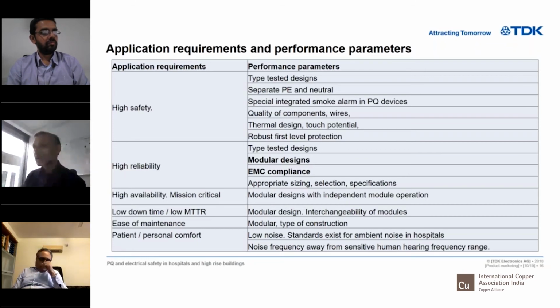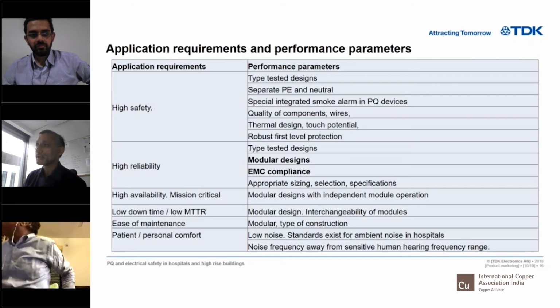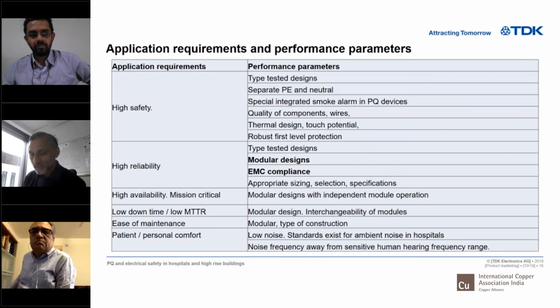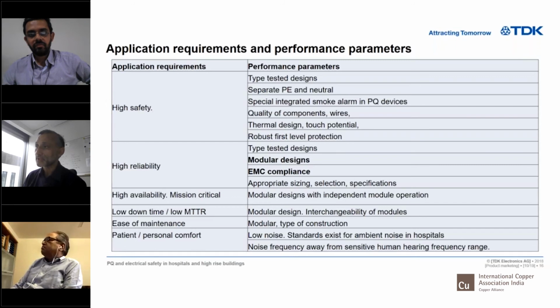when there's a fire. So when you're talking about high safety, everything right from cables to switchgear to power conditioning equipment especially should be a type tested design. And there must be a separate neutral and protective earth. Especially in India, even a good electrician would not know the difference between a neutral and an earth. We think the protective earth is the fourth wire, which is also the neutral, which is the cause of half the problems. Then in most cases, if you read the Abu Dhabi ADDC standards, even for a simple APFC panel, they started specifying five years back that the equipment should have an integrated smoke and fire alarm, so that the PQ device, when it catches fire, doesn't take the building along with it.